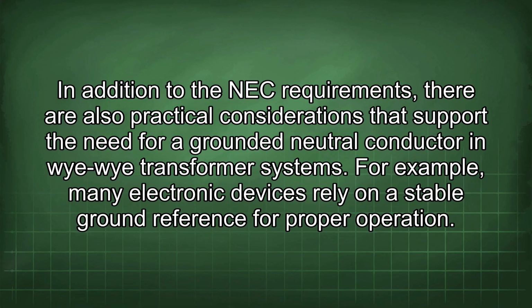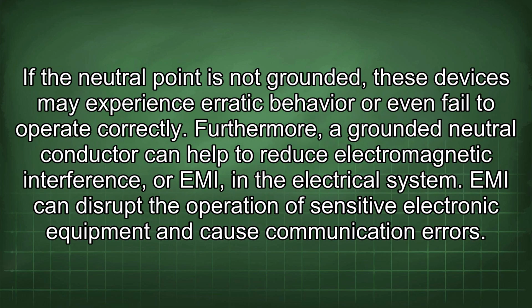In addition to the NEC requirements, there are also practical considerations that support the need for a grounded neutral conductor in Wye-Wye transformer systems. For example, many electronic devices rely on a stable ground reference for proper operation. If the neutral point is not grounded, these devices may experience erratic behavior or even fail to operate correctly.